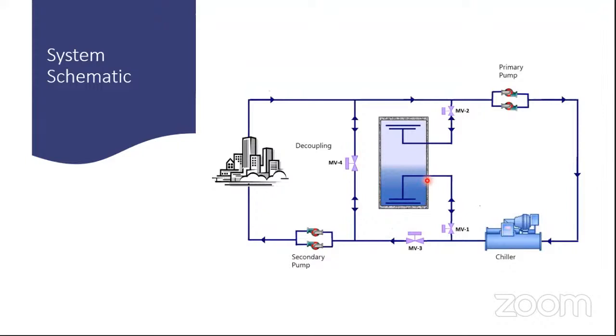There could also be a case where only thermal energy storage is cooling. In that case, the chiller will not operate, and nor the primary pumps. And in that case, the secondary pump is drawing the desired amount of flow corresponding to the load, and the chill water is drawn from the thermal storage tank. So from here, the warm water we see is returning back. After the load, the return water is warm and it is going back. So it'll go back to the primary pump. It'll come back to the thermal storage tank as well.